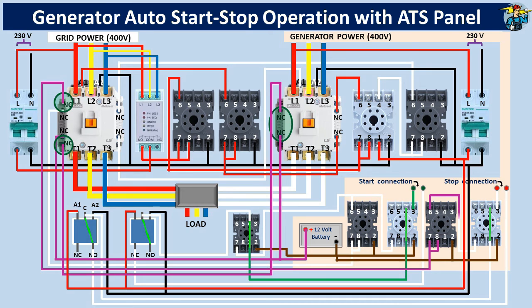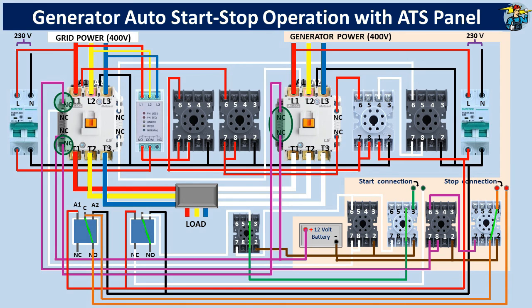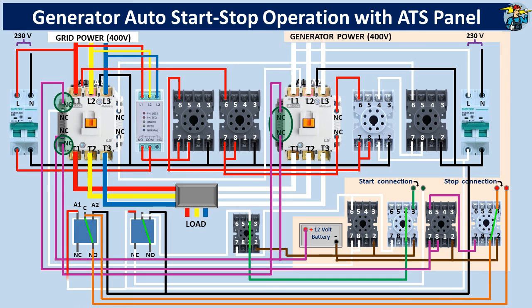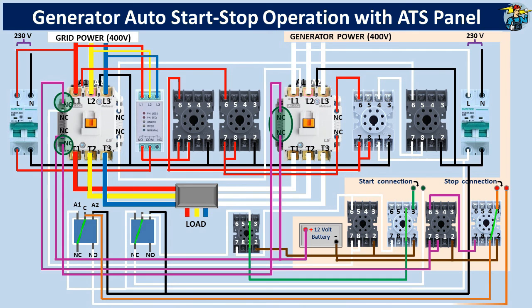After this delay period, the engine stop relay is activated, causing normally open ports 1 and 3 to close. This creates a loop to join the generator stop connection points via the 5-pin SPDT relay and the stop relay. With it, the engine stop solenoid, which opens the fuel supply line to the engine, is deactivated and the fuel supply to the engine is closed. After the generator stops, control power to the SPDT relays will be removed, disturbing the engine stop connection loop. However, this will allow the generator to be started or stopped manually using a push button switch or a key switch for maintenance or repair work. Be sure to manually turn off the generator control breaker to prevent it from automatically loading during a power outage.